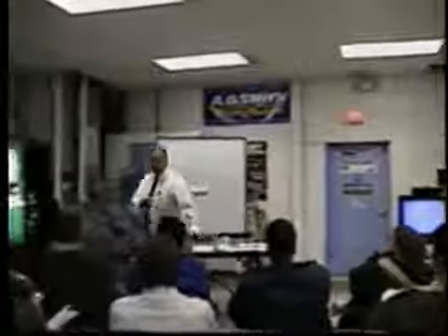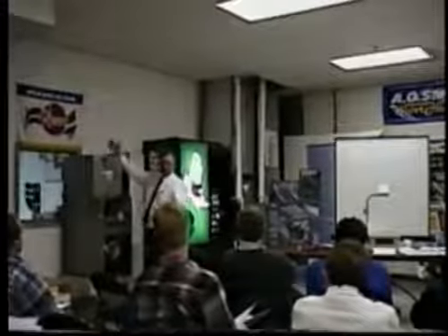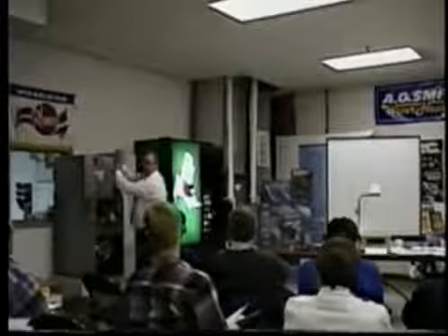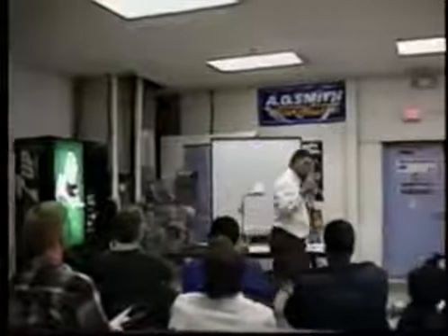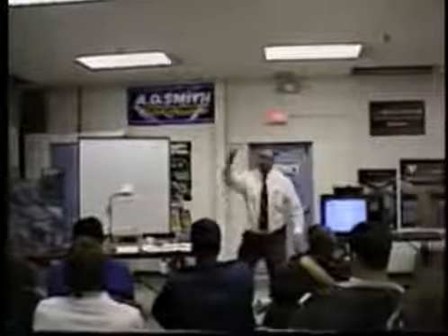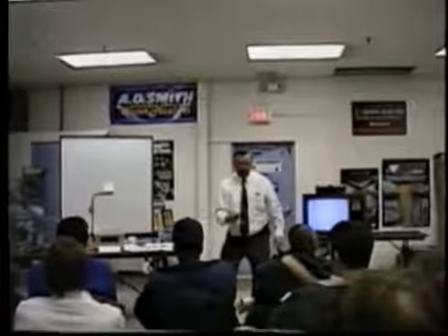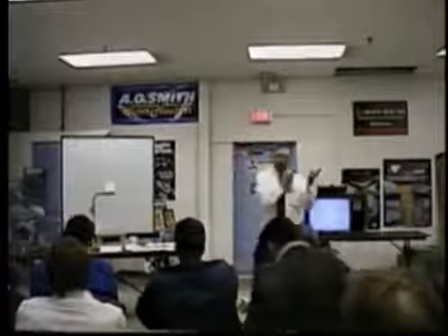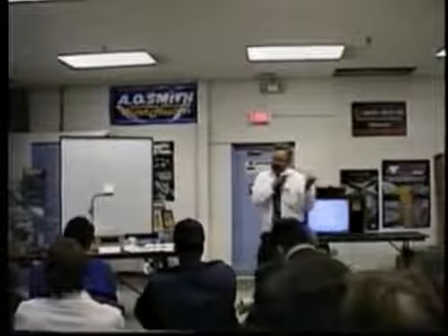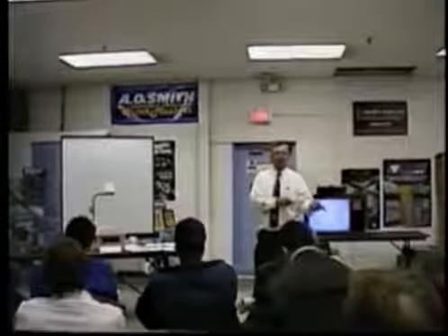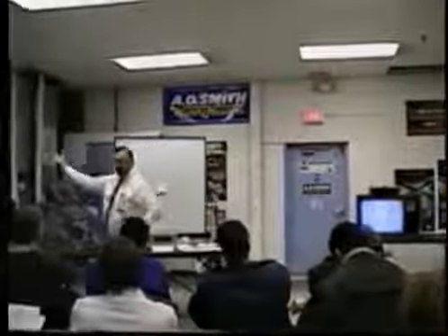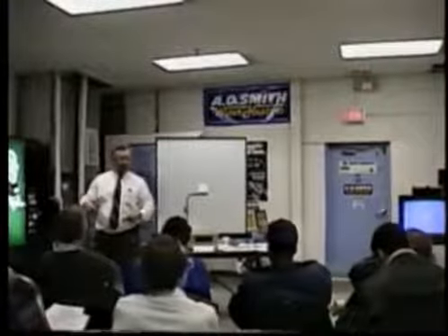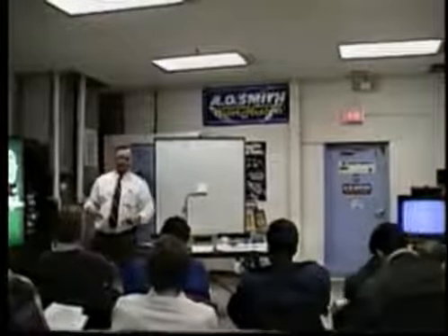This is how air conditioners work. As the air comes through, it gives up the BTUs, cools the air, maybe, but it condenses the vapor. And the point is this: for every pint of water that goes down the drain, the air conditioner had to remove, from the vapor that went through the coil, 970 BTUs per pint.